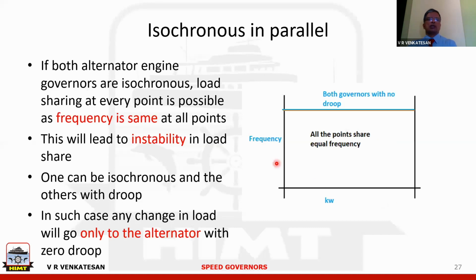Now coming to this isochronous condition. What is the rule for running in parallel as far as frequency is concerned? It has to be the same. It has to be exactly the same. Now if both alternator engines are isochronous, then at every single point the frequency is the same. So it is possible to run here, it is possible to run here, any such position is possible. This will definitely lead to severe instability. It can very often go to a level where all the power goes on one alternator and the other goes to zero or even motoring condition.